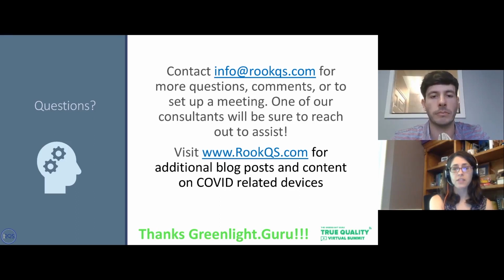And the fees associated with that as well. Anything that you can provide some insight on? No fees in the event of registration being required, which for most of these, like distribution, it's not. We have still seen certain companies or hospital groups that want to ensure something's registered before they buy it. That's the typical $5,300 annual registration fee, but that's not required for an EUA. There's no fee for that.